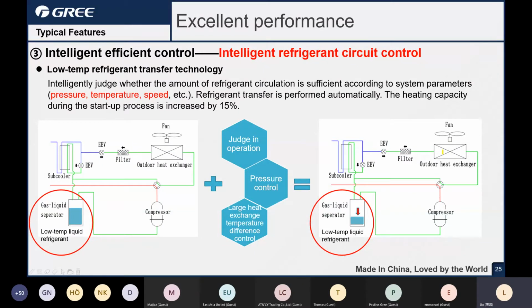Next one is about the refrigerant circuit control. For VRF, not only VRF, almost all air conditioners, there is a phenomenon: low temperature refrigerant transfer, right? If the unit doesn't run for a long time, lots of refrigerant will be stored in the compressor, because of the temperature difference between here and the ambient, it will cause the refrigerant to transfer from the other hot location to this cold location. So after a long time on standby, there will be a lot of liquid stored here.